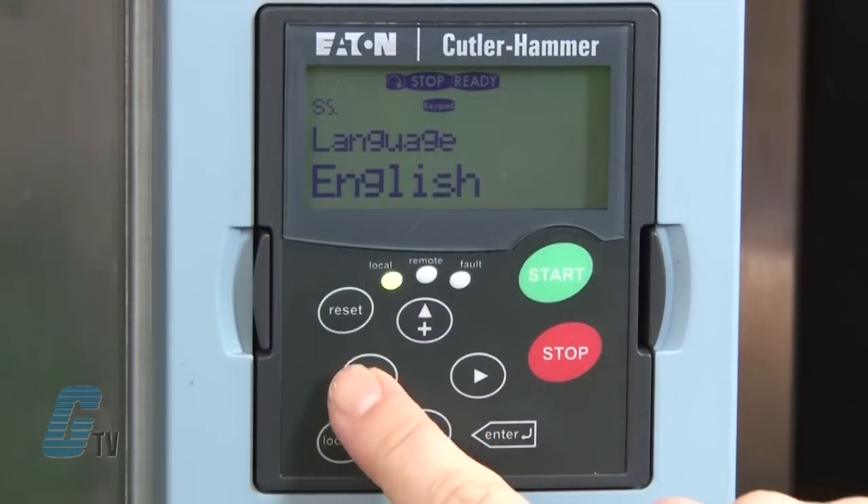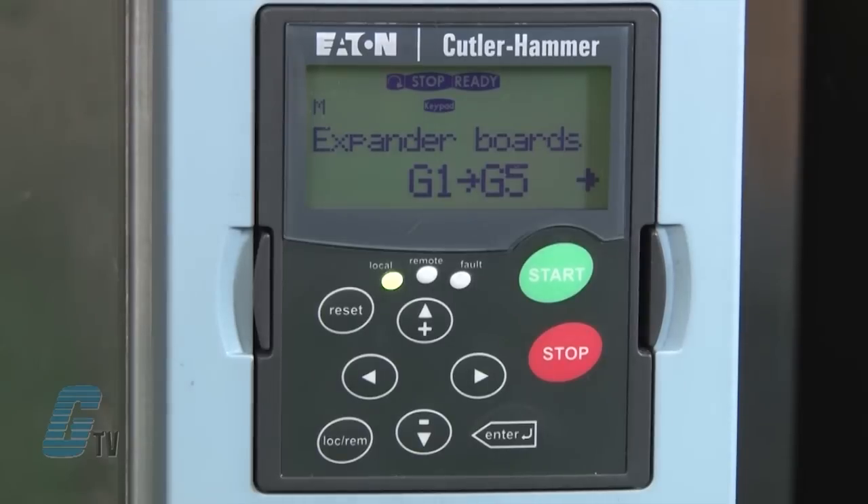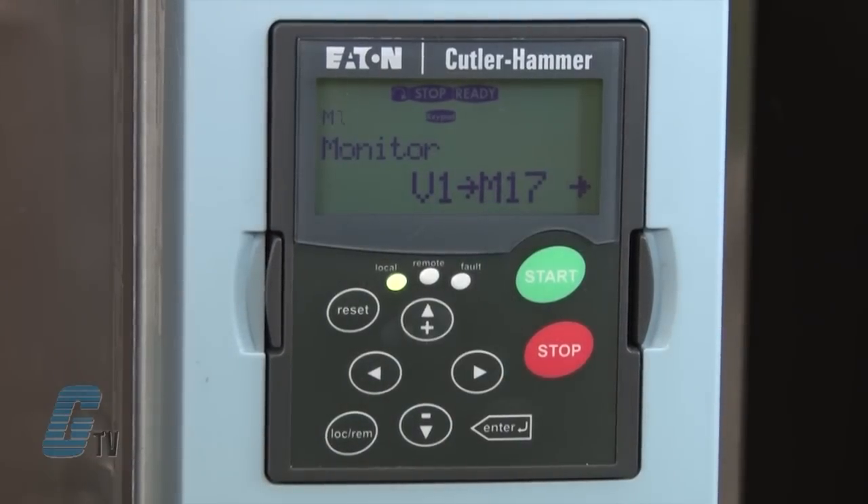I will push left again to the programming menu and scroll up to M6 for expander boards. This is where I can see what expander boards are connected to the control board and access the parameters associated with these boards. For the basic demonstration, I will continue to scroll up to M1 for the monitoring menu. This menu allows me to see the parameter values during operation, including some that are not given in the operation mode.